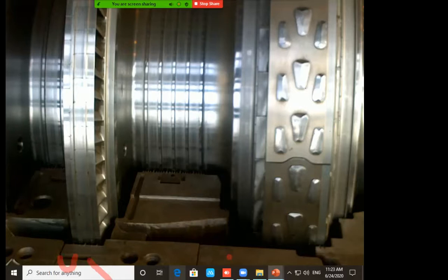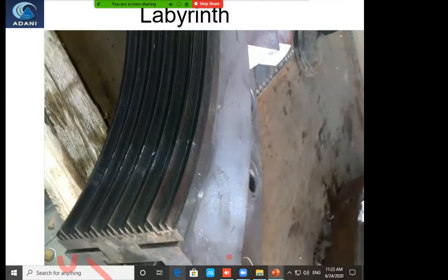That is the sealing area. How is the steam being sealed over here? It should not go out from this passage. Next. That is sealing or labyrinth. How is sealing done? There are a number of labyrinths. They minimize the passage, and the pressure will drop. The high pressure steam will be dropped again and again, and it will lose its pressure ultimately and stop leaking from the outside.